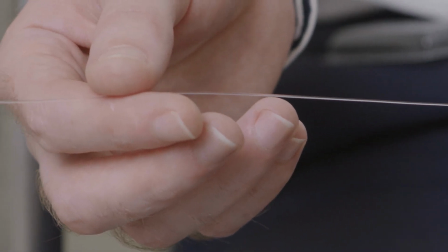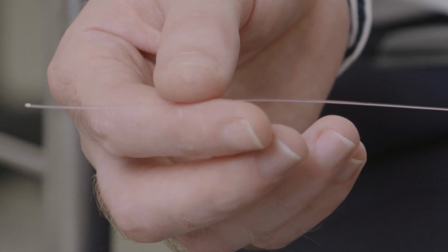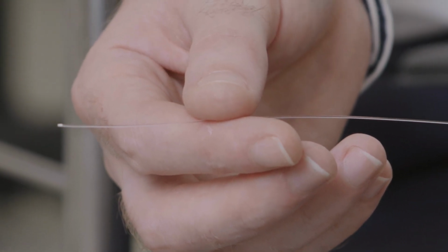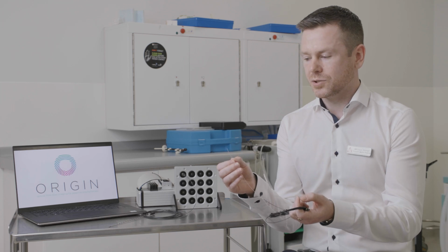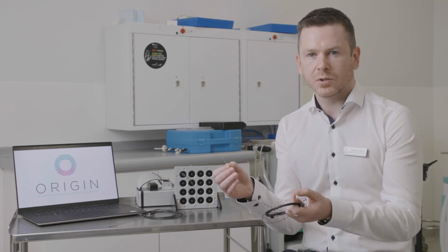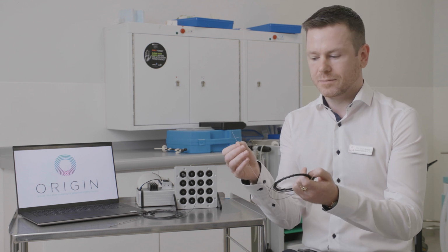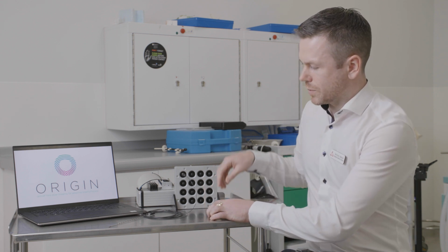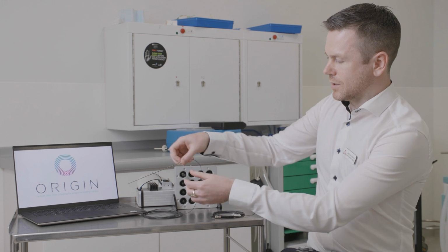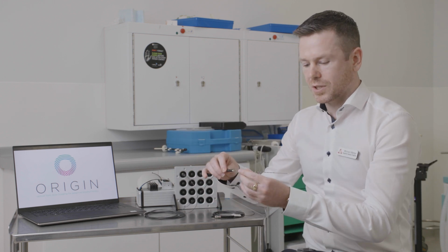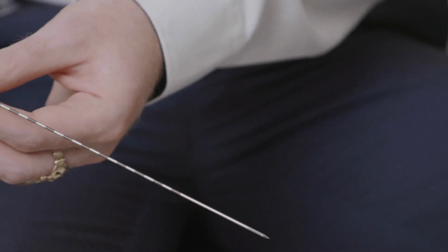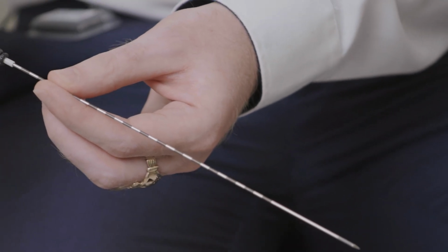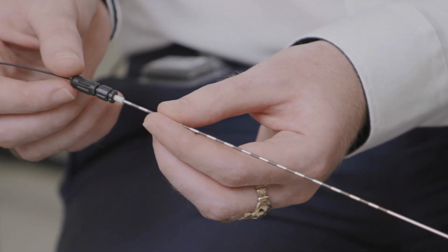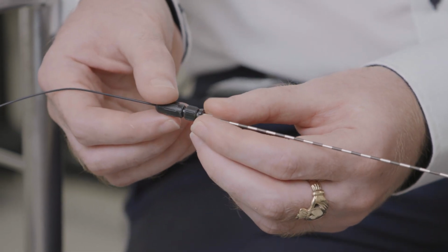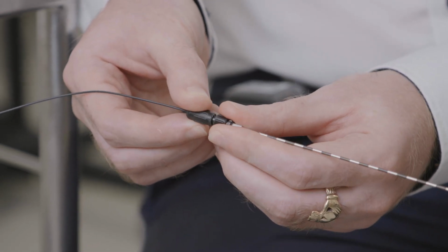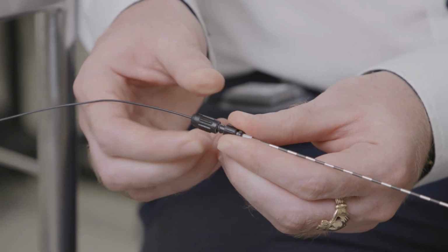And what you can also see here right at the tip of the fiber is our scintillator material. The specific geometry that we've employed was designed to ensure that we optimize the amount of light which is coupled into the fiber itself. I've just also set up here on the side one of our optical fiber sensors which has now been inserted into a clinical needle. And there's a locking mechanism here at the top which ensures that once the fibre is fully inserted, it can be locked into place and then won't move during a treatment procedure.